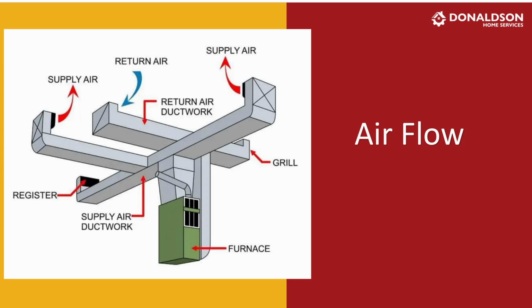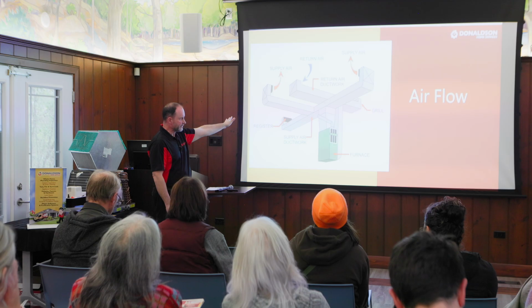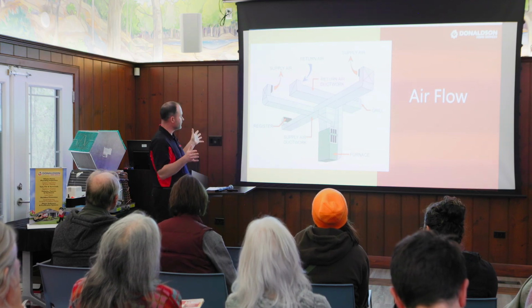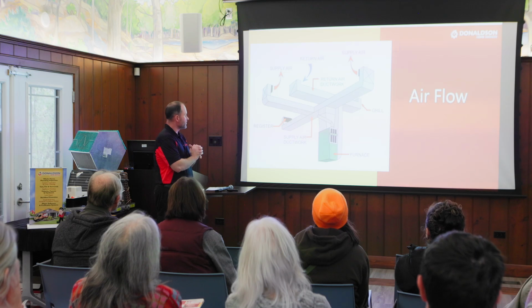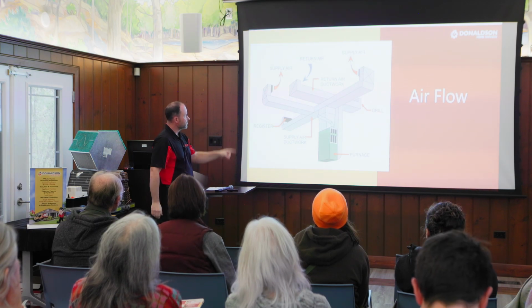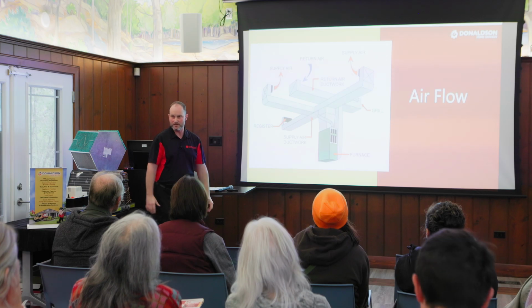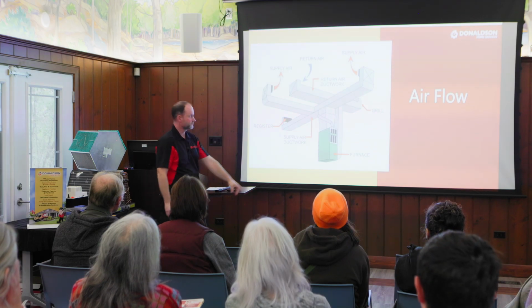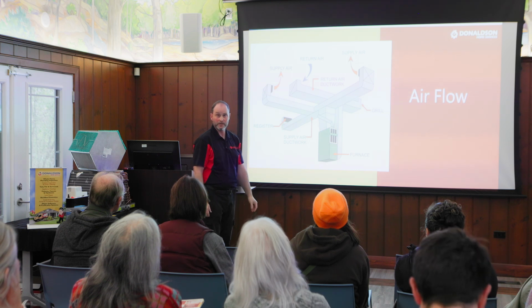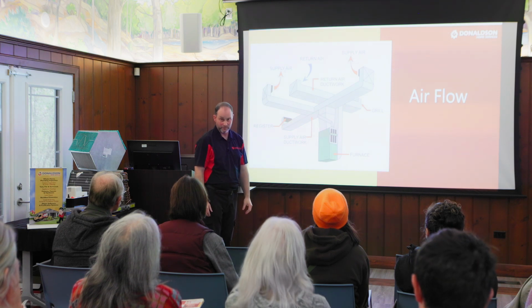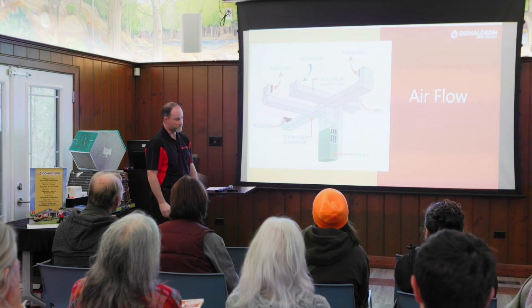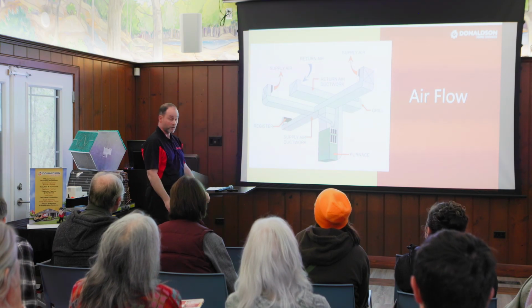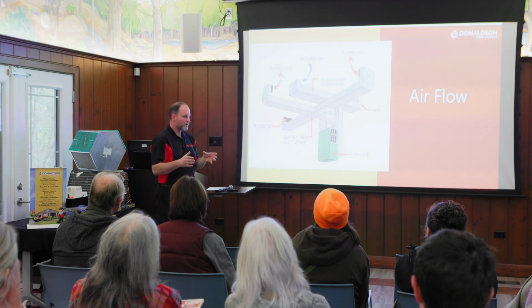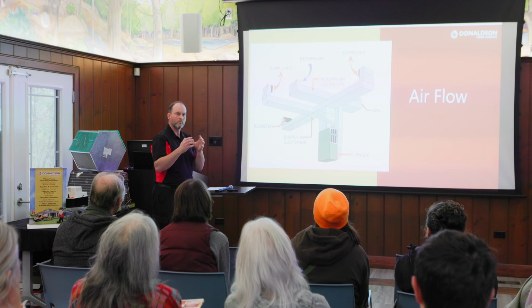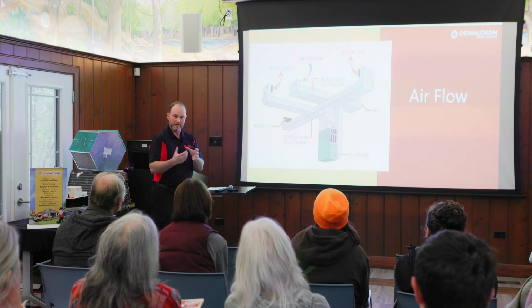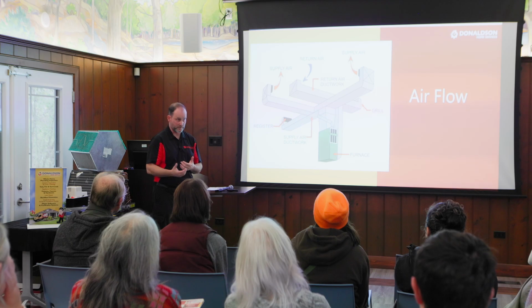Now the second most important thing: airflow. I've been in thousands and thousands of homes doing many investigations, looking over things and trying to make things better. The number one reason for service calls, us coming out because you've got no heat and no cooling, is inadequate airflow. It has nothing to do with your furnace, nothing to do with the components of your air conditioner. It has plenty to do with the airflow in your home. When we look at equipment, the larger the equipment, the more we must increase the airflow with that equipment in order for it to work efficiently and give you the comfort you're looking for.